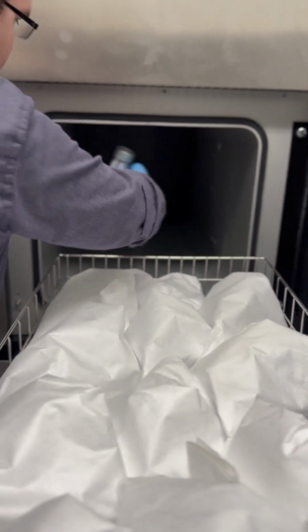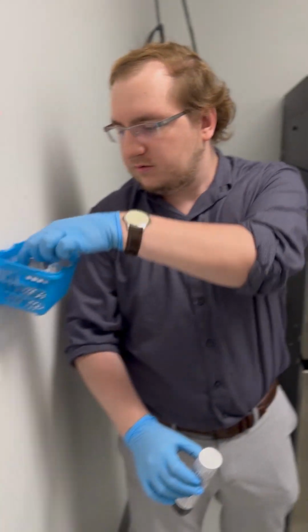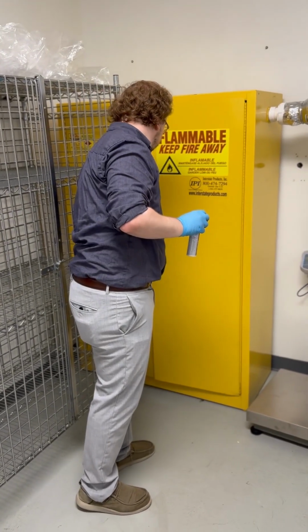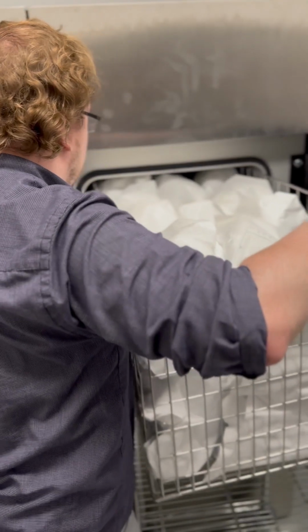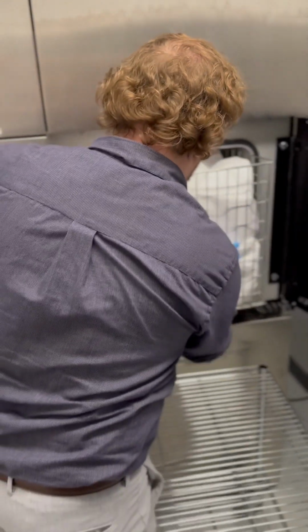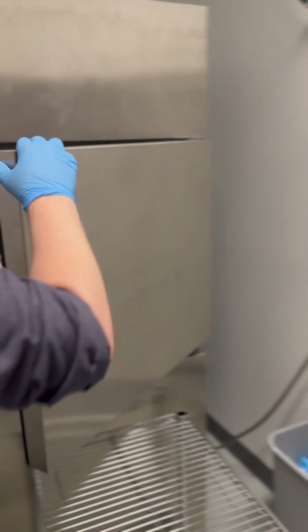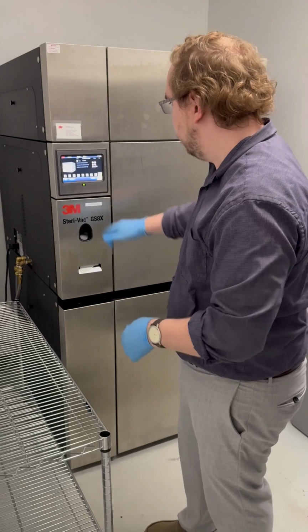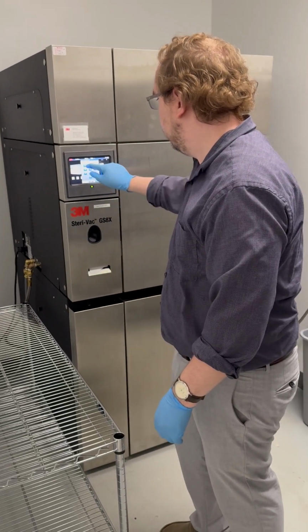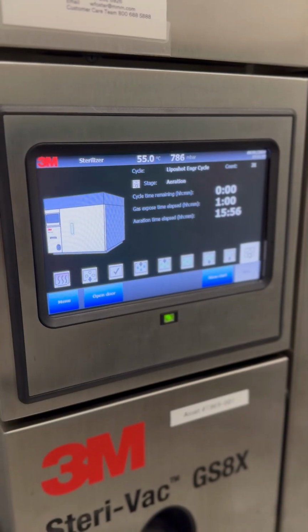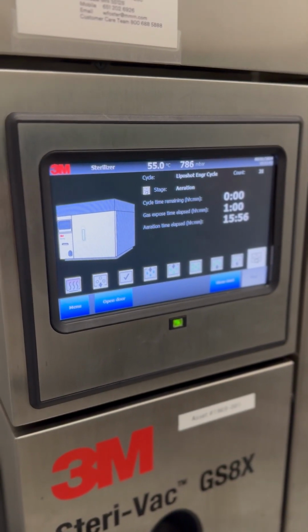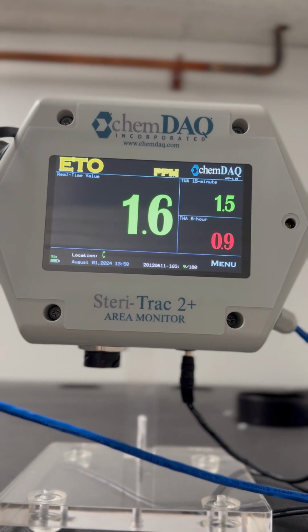And with well-placed BI strips externally and internally, and setting it out for testing, you get a sense of how many bacterial elements are being killed with the fractional cycle. With the half cycle, obviously you want more bacterial elements killed, both externally and internally. And then on the full cycle, you want to show full eradication of those BI strips.